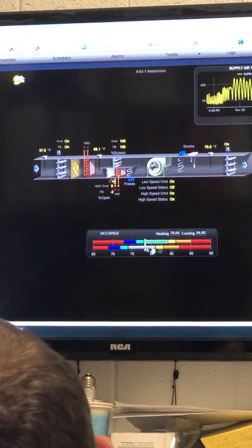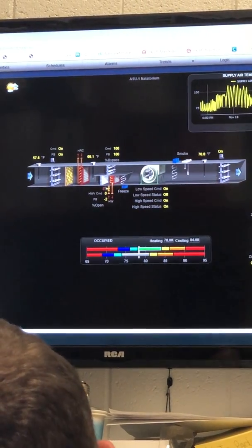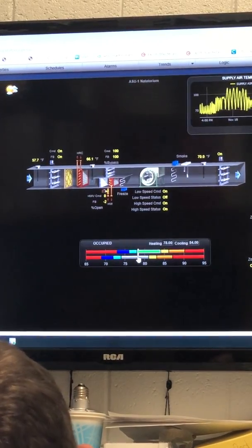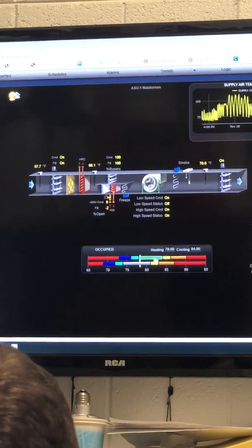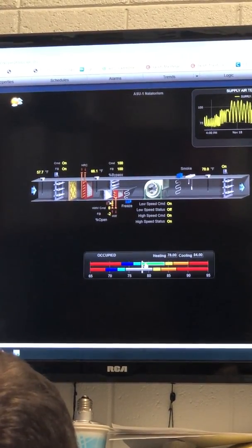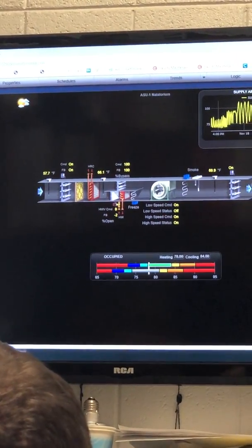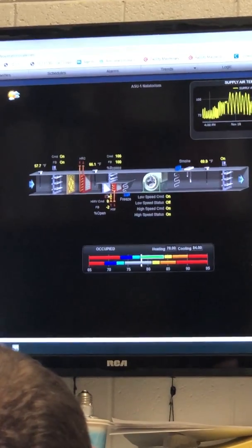So if you look at the graphic, see this green section here, that's the dead band, and it's within that, so it's basically just passively supplying air. Once it drops below this and the hysteresis, then it'll start to heat back up. It'll fall outside of your set parameters, and then it'll take the steps to reheat itself back up to the temperature that you want.